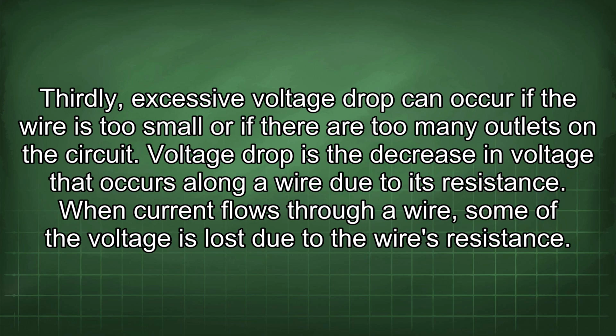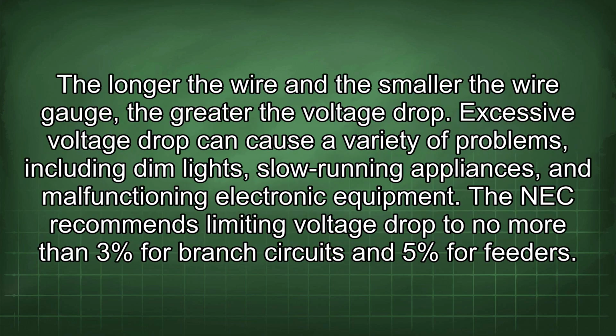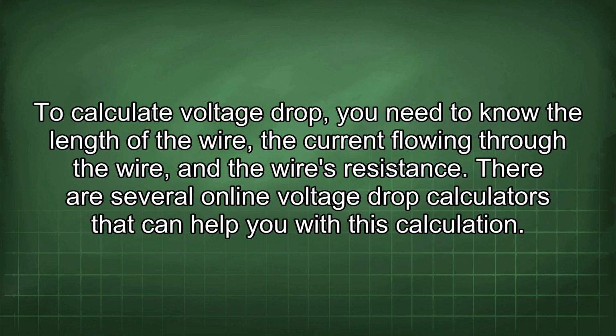When current flows through a wire, some of the voltage is lost due to the wire's resistance. The longer the wire and the smaller the wire gauge, the greater the voltage drop. Excessive voltage drop can cause a variety of problems, including dim lights, slow-running appliances, and malfunctioning electronic equipment. The NEC recommends limiting voltage drop to no more than 3% for branch circuits and 5% for feeders. To calculate voltage drop, you need to know the length of the wire, the current flowing through the wire, and the wire's resistance. There are several online voltage drop calculators that can help you with this calculation.